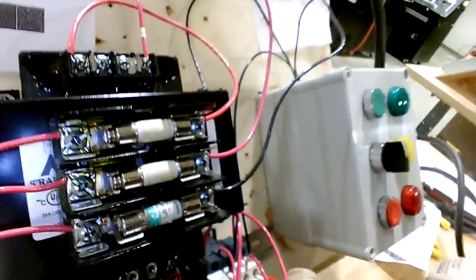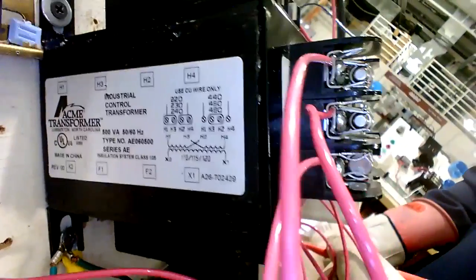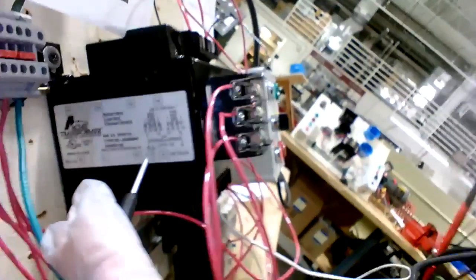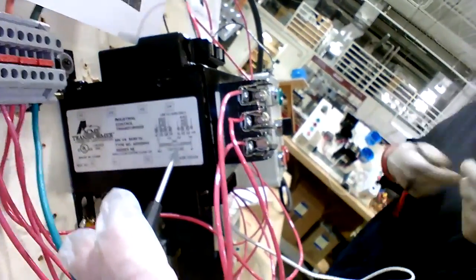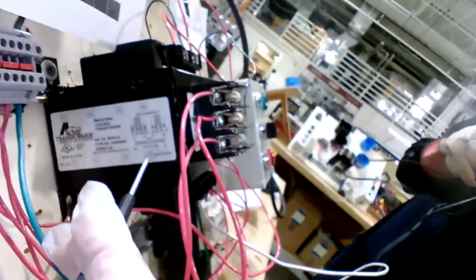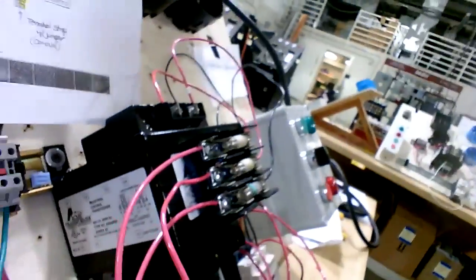Right. It's a little bit low because you're feeding 208 into the transformer, and the transformer is designed for 220 to 240 on the incoming. If you look over here on the side, for an incoming voltage of 220 on that transformer, you would get 110 coming out. At 230, you get 115 out of it. At 240 coming in, you get 120. Well, we're feeding in less than 220, we're feeding 208, so you're getting 107 coming out. It's proportional. This thing steps it down exactly in half, so you get half of what's coming in. So anyway, that's your basics on doing your readings on the circuit.